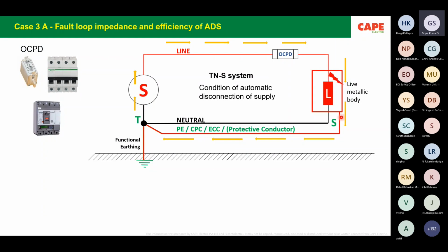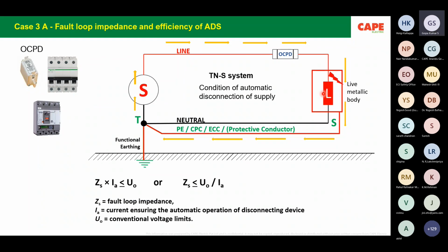If you have a fault, the fault current is returning back to the source. Please note that fault current never goes to earth. It will return back to the source. In this case, there is a metallic fault return path. As a result of the metallic fault return path, you have a loop with a very low impedance. Now the impedance of this loop decides the amount of current flowing through the fault, and that particular current decides the disconnection time. It's very simple to understand. Simple Ohm's law.